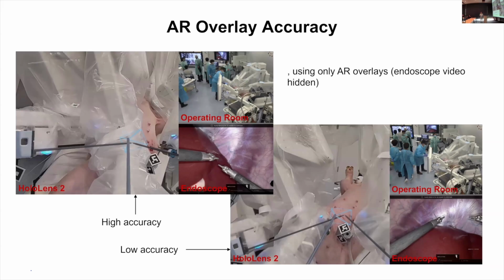Well, in my opinion, it probably is, because mainly they're using the display, or a big use of it is to get the instrument into the field of view. And the field of view looks big, but they're actually zoomed in very often, so maybe just a couple centimeters. When we asked the surgeon, they said they wanted about a centimeter of accuracy. So we don't have that.